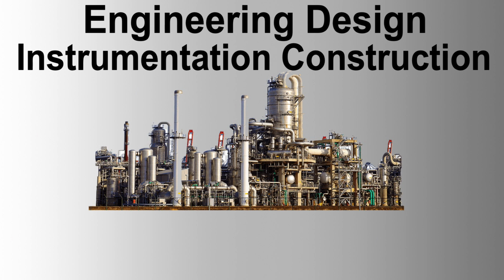Instrument air supply headers. Instrument air supply headers piping shall be galvanized. Subheaders to users, including secondary and tertiary loops, branching off the main header shall be connected to the top side of the pipe. Each takeoff is provided with an isolation valve. Spare takeoff from the headers will have a valve, the free end of which shall be plugged by means of a nipple and screwed cap.